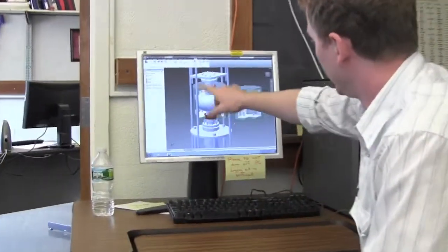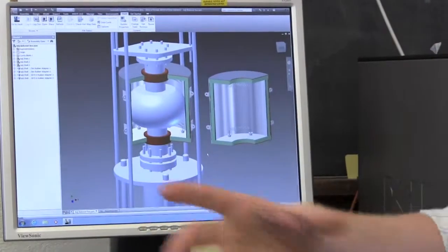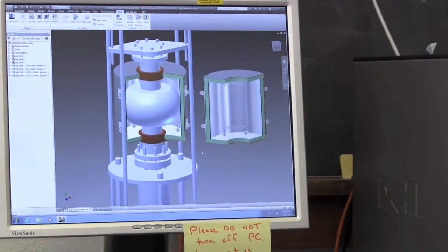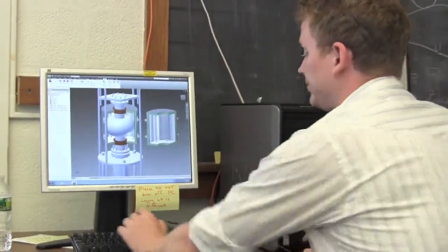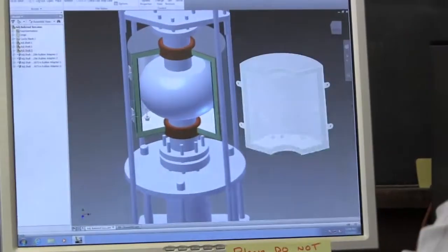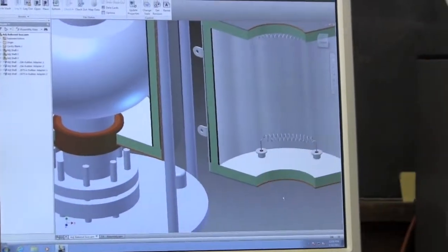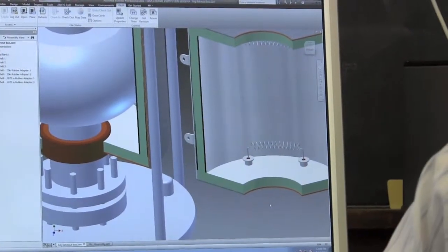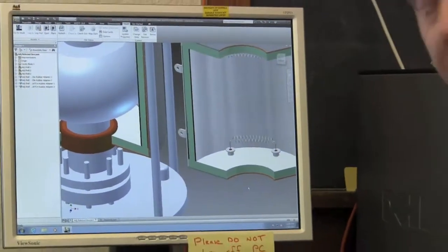It needs to be a modular system. Here I've just made a quick mock-up of the tightest constraint for a baking test stand. As you see, it is in 3 sections with several different layers of insulation. Here we have our electric heating element. This is currently in fabrication, but maybe we can show you a little bit about the control system.